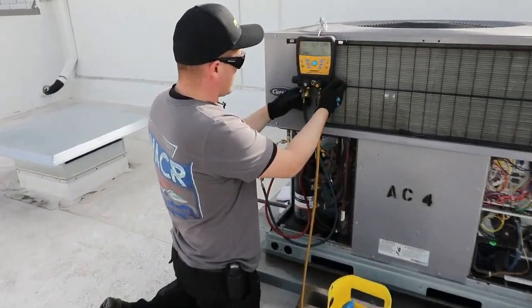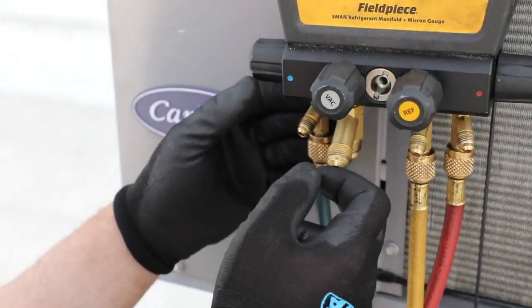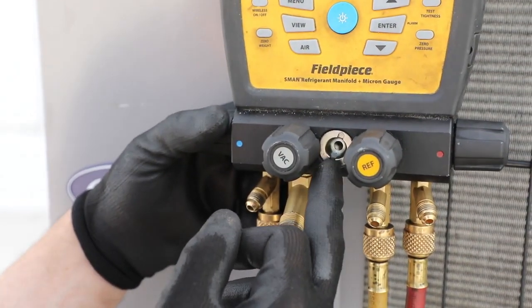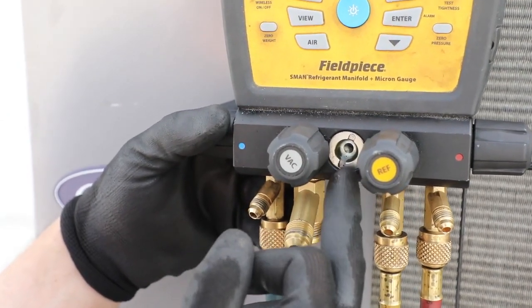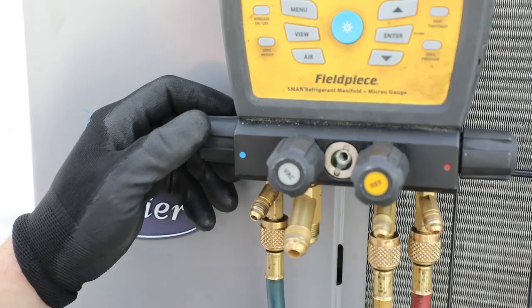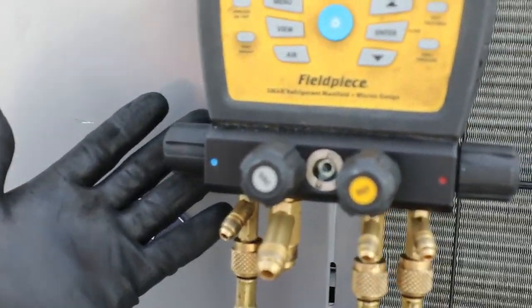Another really cool feature about the Fieldpiece manifold is the sight glass on here. They actually changed the sight glass from the older models and made it a little bit easier to see the liquid in the system, so you're able to know whether you've got liquid as you're charging. In this situation there's no liquid — we're just charging vapor at the moment.